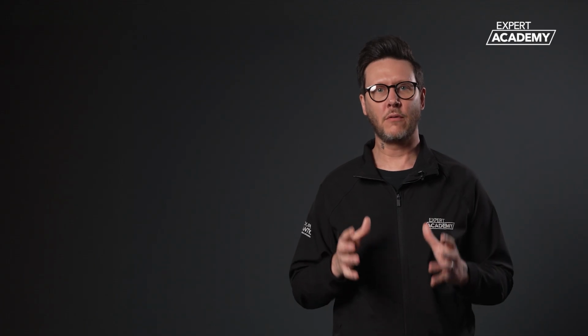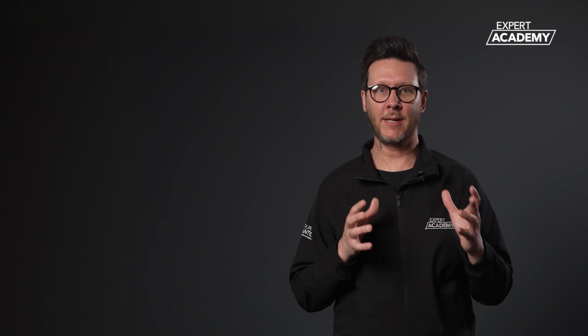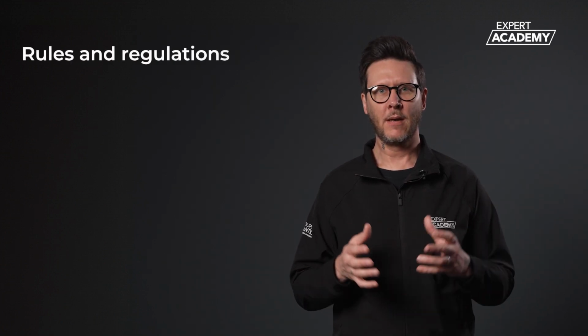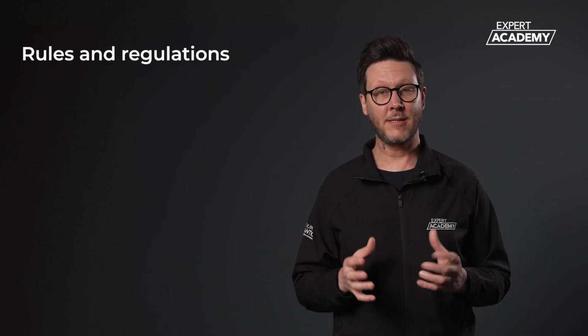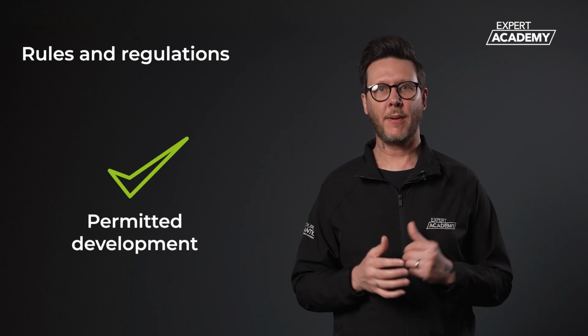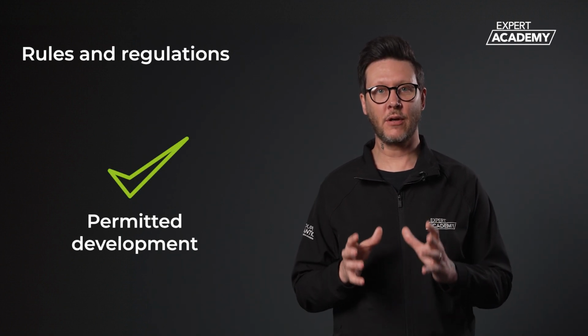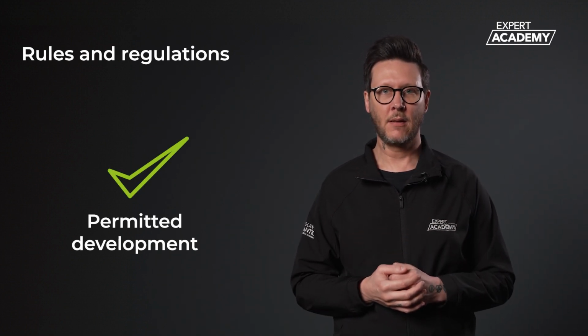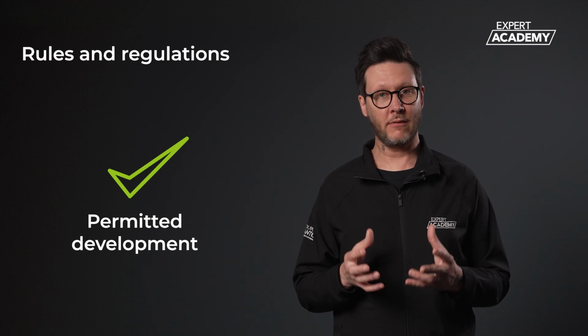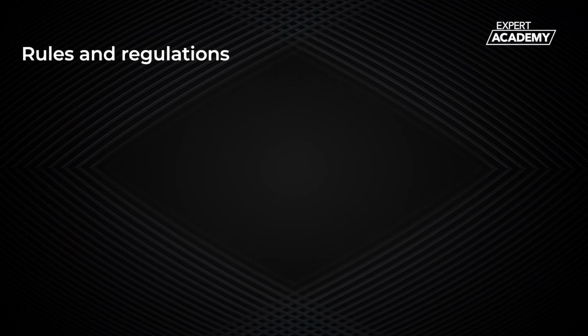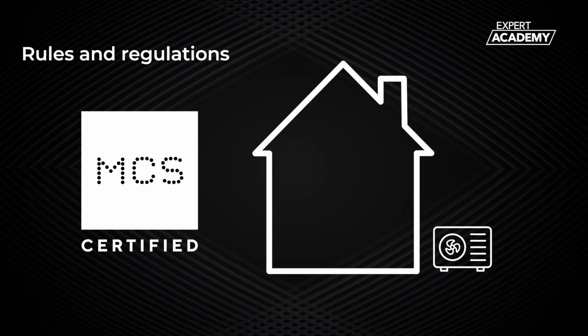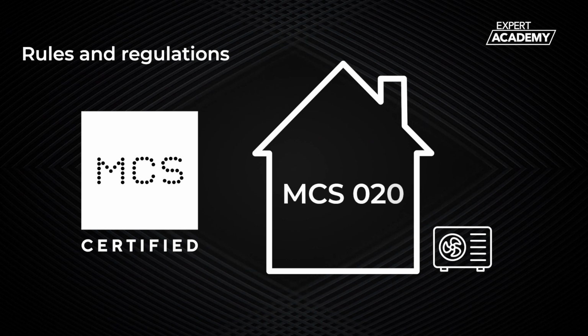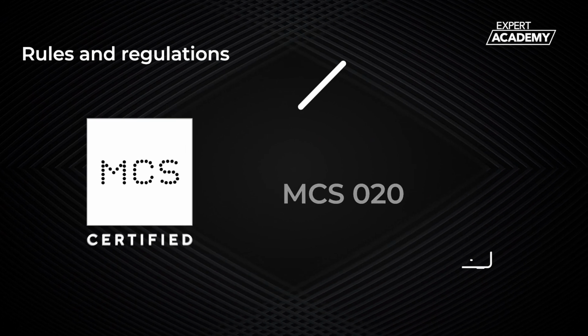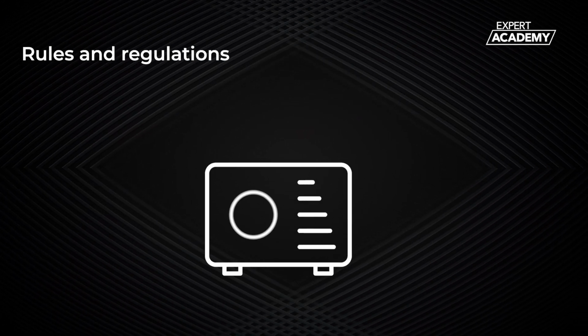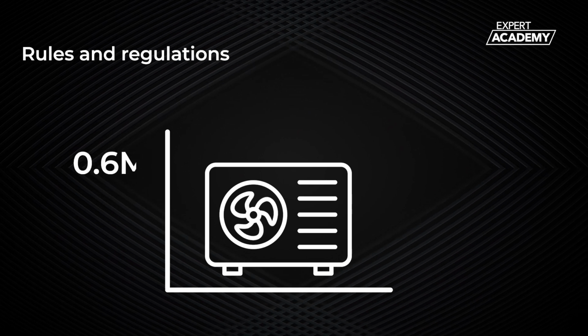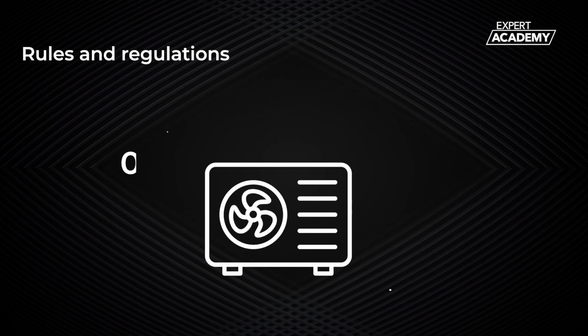Let's now move on to the rules and regulations around heat pump installation siting. Heat pumps are considered to be a permitted development, not requiring planning permission provided certain conditions and limits are met. A few of these main conditions currently are: the installation must comply with MCS planning standards, MCS 020. The volume of the heat pump's outdoor unit must not exceed 0.6 cubic metres.